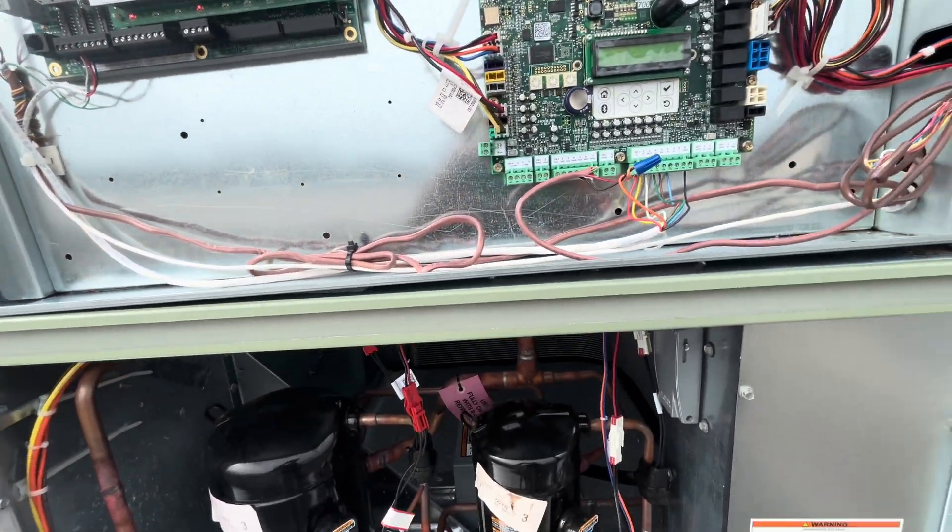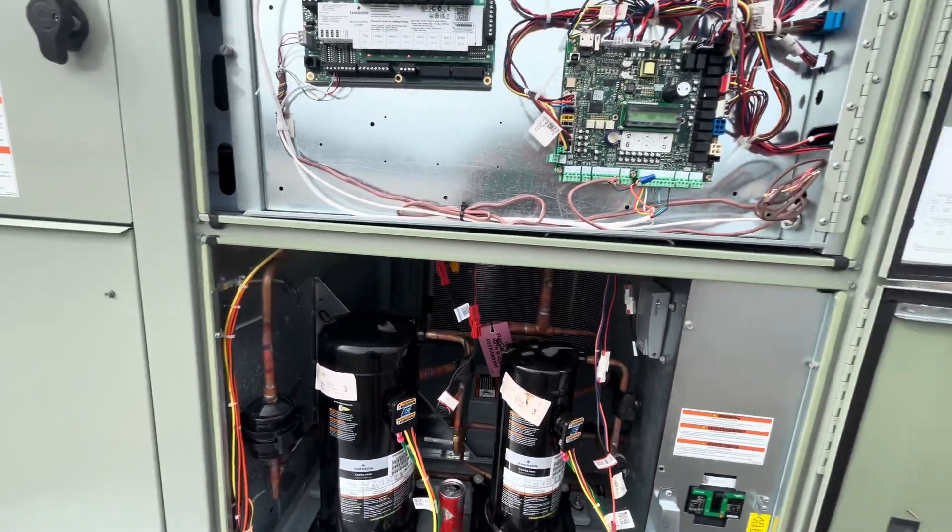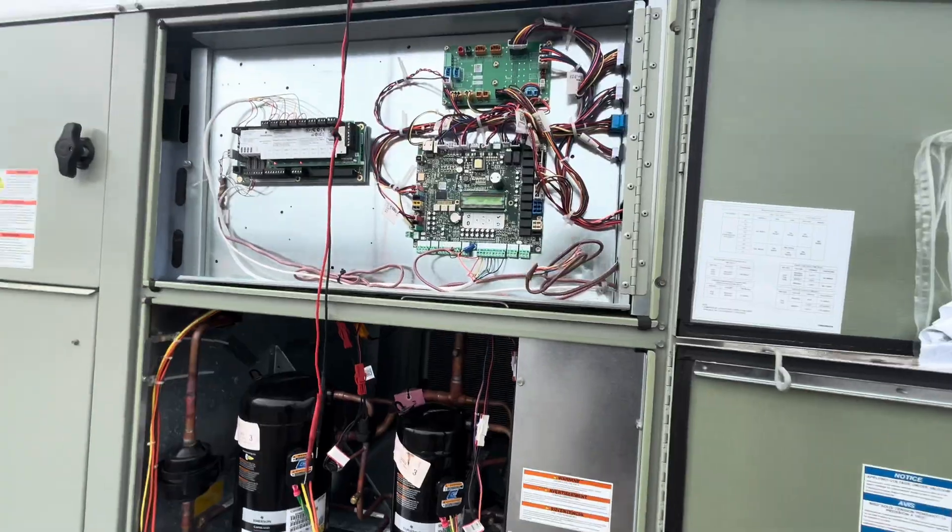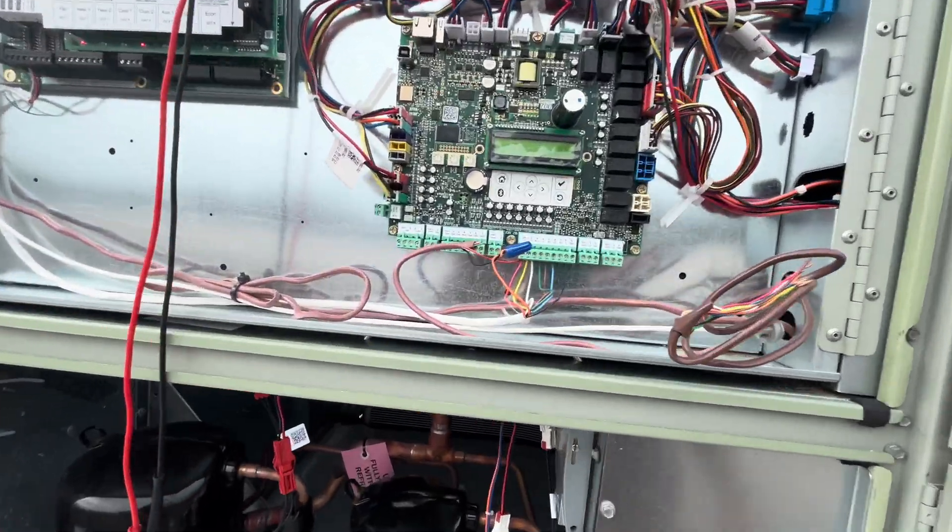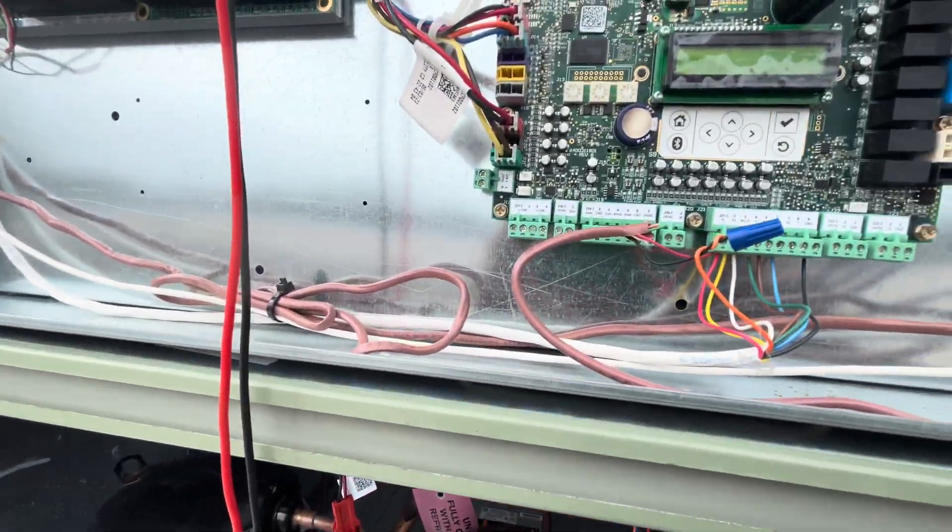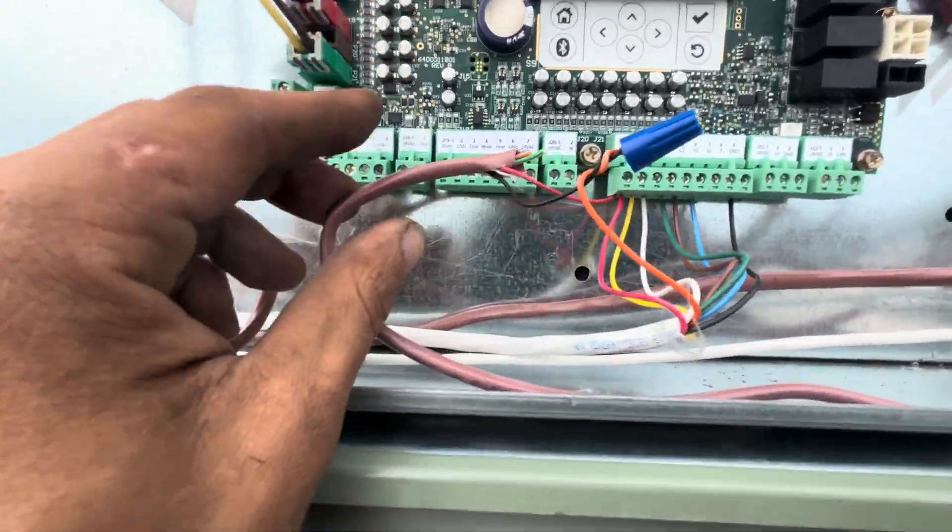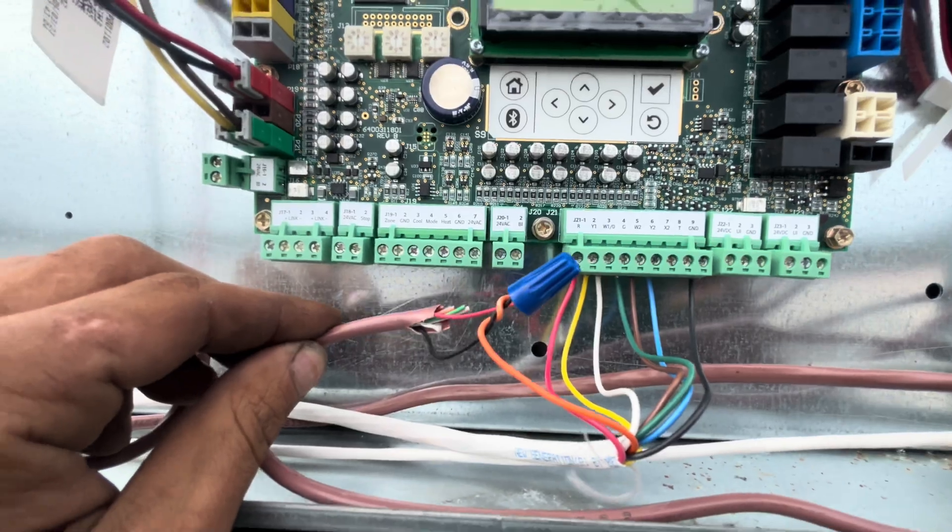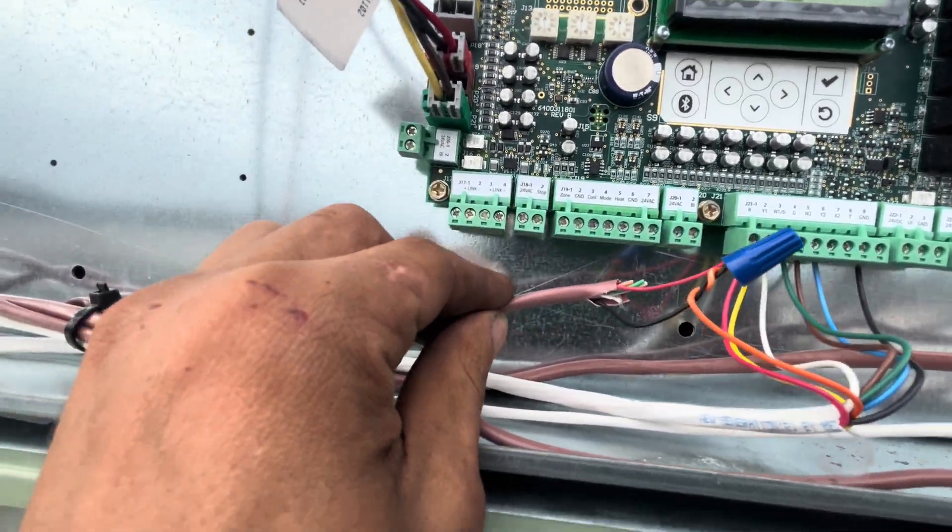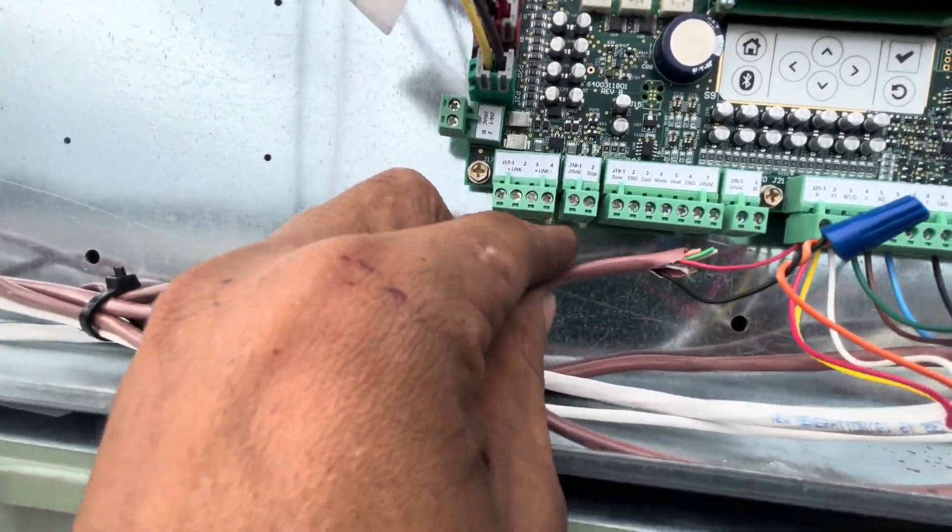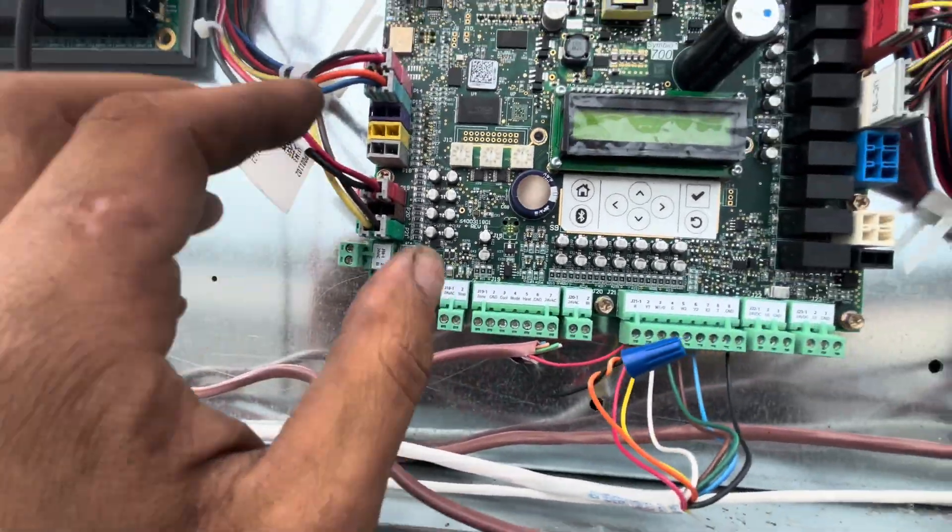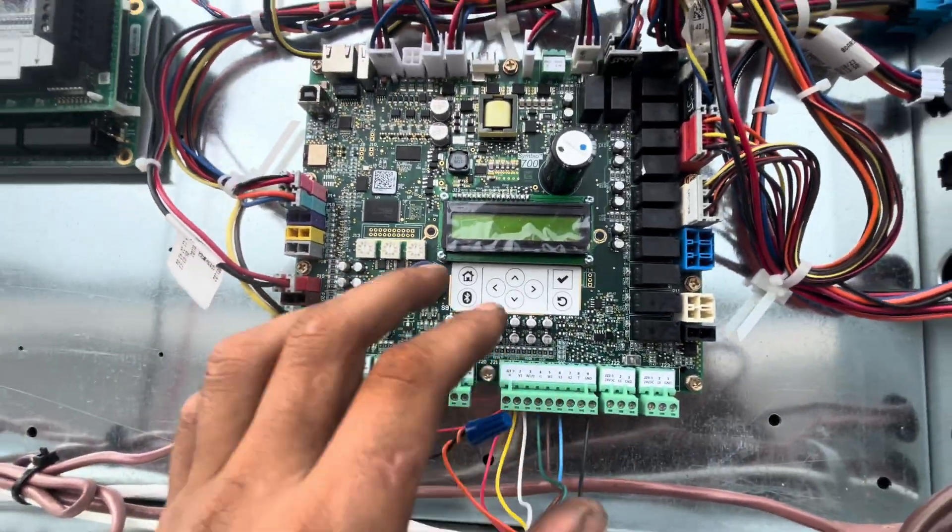...plug each connector in one by one. And then, whenever you plug a connector in and that display goes blank, that connector and that circuit is your problem. And that's where you need to investigate.